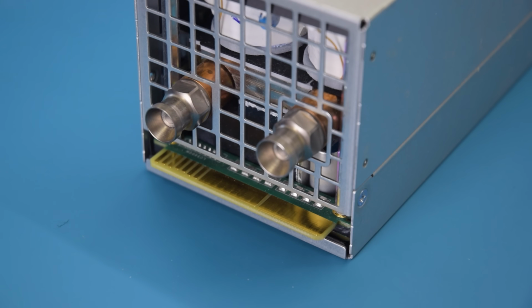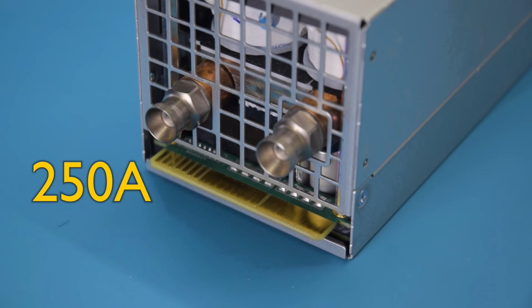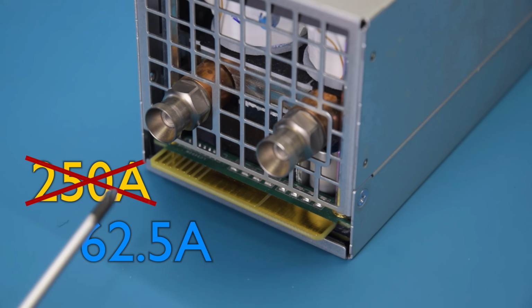The reason for that is that to get 3000 watts out of this power supply at 12 volts, these contacts, and all of the traces in the motherboard and wiring and things like that, have to carry 250 amps, which is insane. Quadrupling the voltage to 48 volts reduces that current requirement by 4 times to a much more manageable 60-ish amps. But that's less exciting.